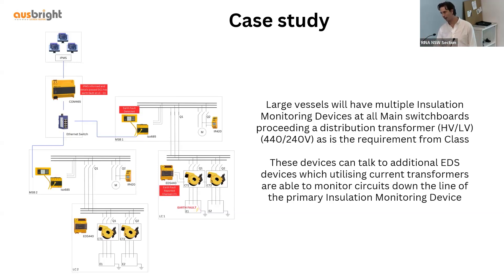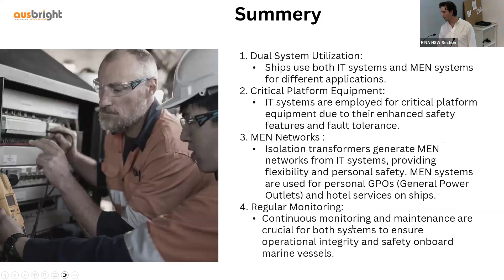All modern insulation monitoring devices are now connected to the platform management system, so maintainers are continually getting updates on the condition of insulation across the vessel, as all devices can now communicate via Ethernet bus or Modbus. IT systems are used on vessels, while MEN systems are also used on vessels but mainly in areas where distribution is for hotel services or GPOs for cabins — and you'll have a mix of both networks using isolation transformers to reintroduce the Earth-neutral link.